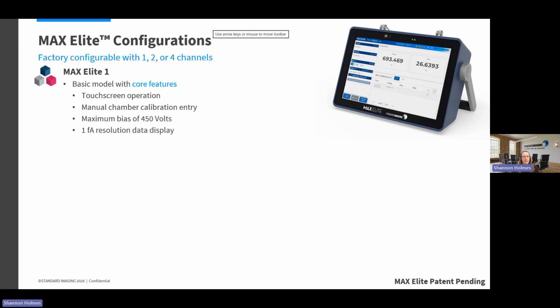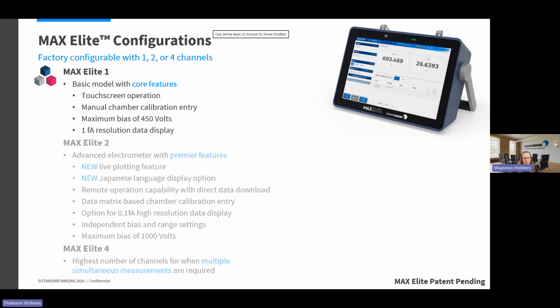The Elite is available in 3 different configurations. They're factory configurations for a single channel, 2 channel, or 4 channels. The single channel electrometer is the basic model. It has the core features that you need, but is a little bit more budget friendly because we've taken a couple of things out. It has, of course, the touchscreen. It does not have the camera, so you would have to enter your chamber calibrations manually if you're using the electrometer for your dose calculation. It has a maximum bias voltage of 450 volts, so that will handle most of your ionization chambers. And it provides you with a femtoamp resolution on the data display.